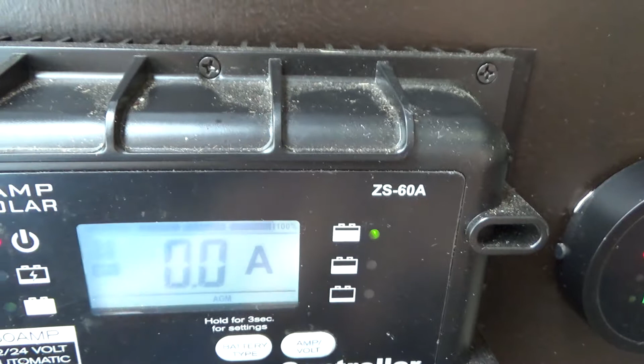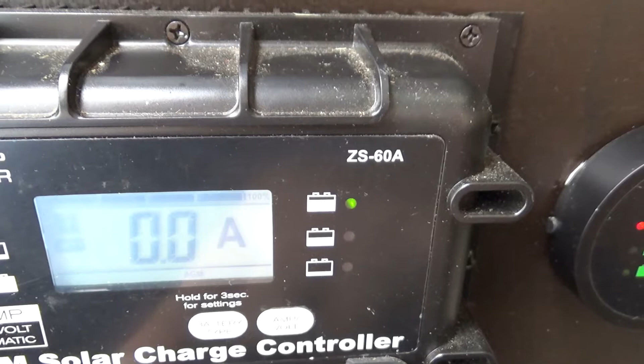The positive cable went through a whole network of relays, some of which were overheating and automatically tripping and coming back on. That's what was the problem with this. So these cables go directly to the batteries now. That fixed that issue.